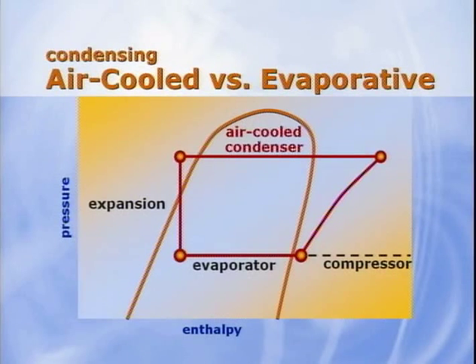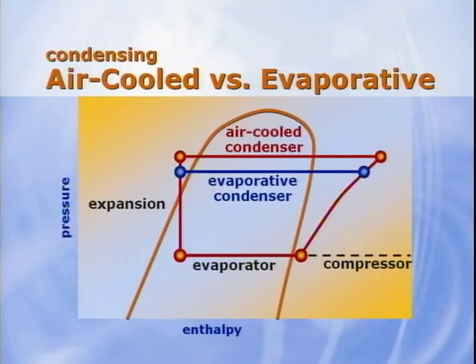Typical design condensing temperatures for air-cooled machines range between 115 and 130 degrees Fahrenheit. Typical design condensing temperatures for evaporative-cooled machines range between 85 and 105 degrees. The lower condensing temperatures produced by evaporative cool condensing reduce the amount of work required by the compressors. The system operates at lower head pressure and therefore reduces the compressor kW. In some systems, evaporative cool condensing can significantly reduce compressor kW, typically between 20 and 30%, and substantially increase energy efficiency over comparable air-cooled systems.